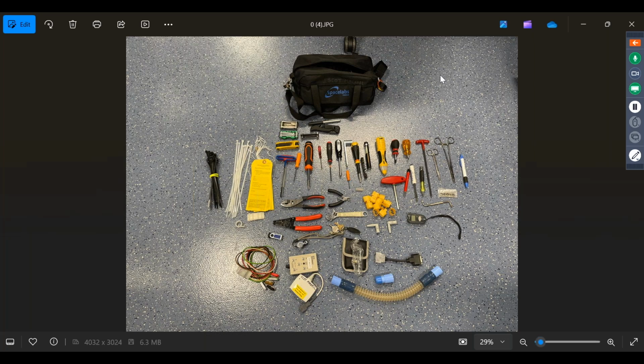These are flow sensors for the Draeger Apollo because the anesthesiologists get really testy when their gas flows aren't registering. And you can do those in 45 seconds in the room. So you tell the anesthesia MD, so you got a flow cell problem. So can your patient take 45 seconds of apnea? They say, yeah, I pretty much think so. I say, all right, we're going to pre-oxygenate. And then when we're ready, I'm going to have the flow cells out on the tray here ready to go.